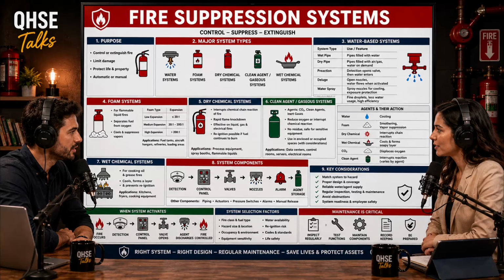The heat melts the fusible link. But instead of water coming out, the pressurized air rushes out of the open head. As the air escapes, the air pressure inside the pipes drops rapidly. And that breaks the balance of the clapper valve. Exactly. The massive water pressure pushes the valve open, rushes into the piping network, travels to the open sprinkler head, and discharges onto the fire.